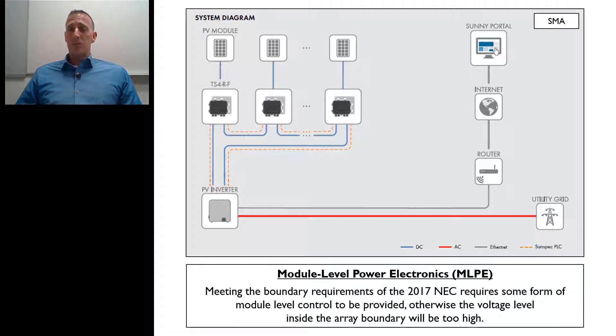I have not seen a product that allows a traditional string system to be there and operate and meet the rapid shutdown requirements. Every system that meets the rapid shutdown from what I've seen now are going to actually have included some form of module level control.